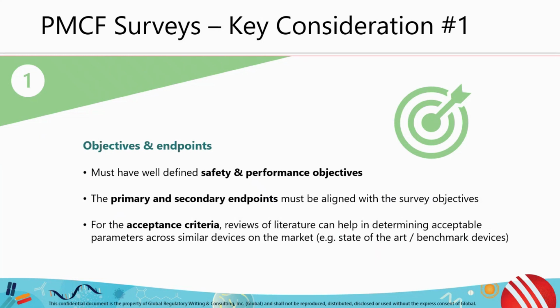And then, like I said, alongside those endpoints, you need to set acceptance criteria. It's really important to review literature, which can help determine acceptable parameters, or look at similar benchmark devices, state of the art, across on the market.